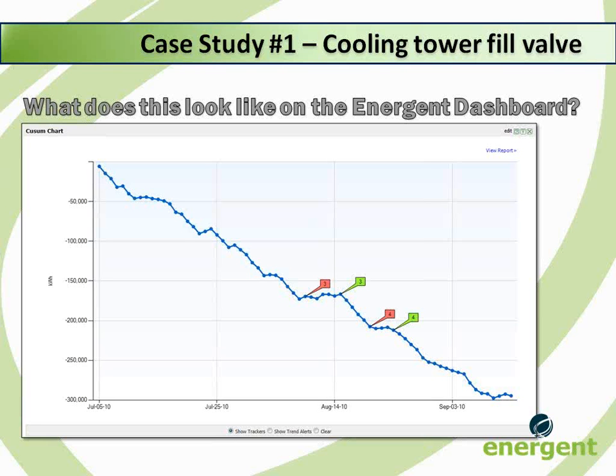This is actual client data from our hospital and what the energy analyst and operator would see. Typically, this hospital saw a very nice savings trend, a smooth downward Cusum. But notice at the beginning of July and periodically throughout the month, there would be these blips on the slope that are circled in red. Between these times, the slope continued to be very strong. But what happened? What was the cost of each of these plateaus? Well, let's look at some of the specifics.